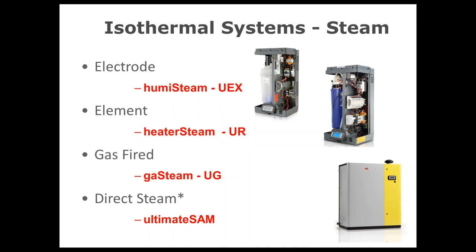The resistive element humidifier uses a permanent tank with a resistive element immersed inside. Upon the call for humidity, the element heats up, similar to an electric water heater. Since minerals in the water are no longer needed for operation, reverse osmosis or DI water can be used. Softened water is still not recommended as it causes foaming inside the tank.